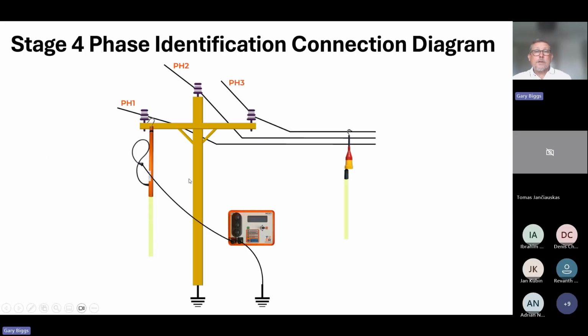So this is a diagrammatic again of what's going on. We've still got the unit there with the voltage measurement point there. We've got the earth connected, the pole itself, although as I said, it is an insulator, but it's an insulator that is connected to earth. And here we have the wireless WPC, the wireless phase checker, and in the case of this one, it's on phase 3, and obviously we're at the end of that range. You'd normally start phase 1, phase 2, phase 3, and we'd test that accordingly.